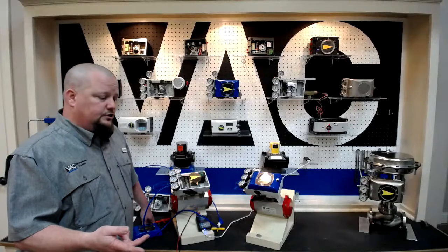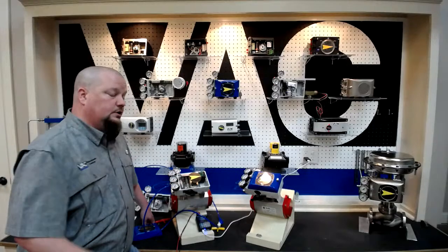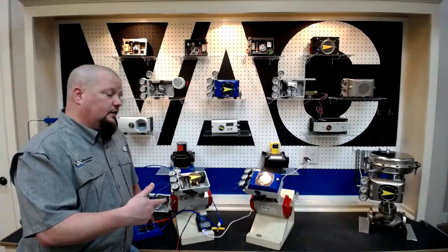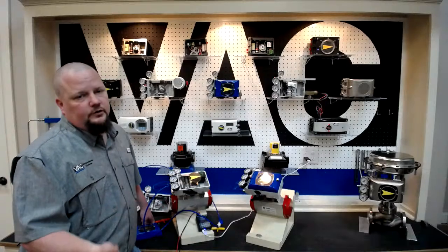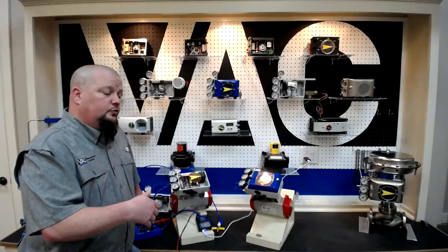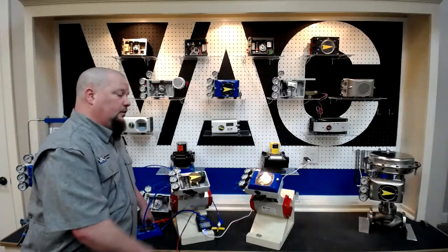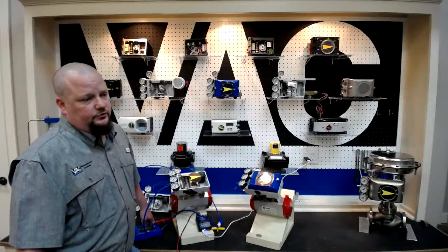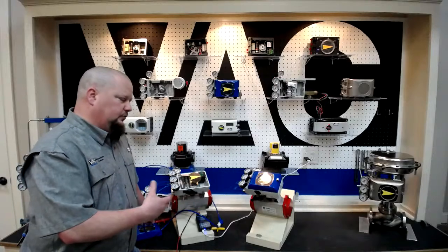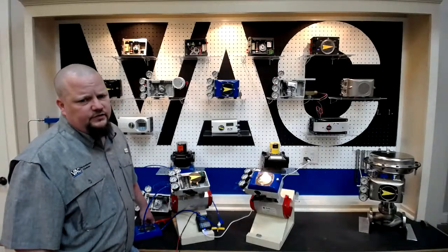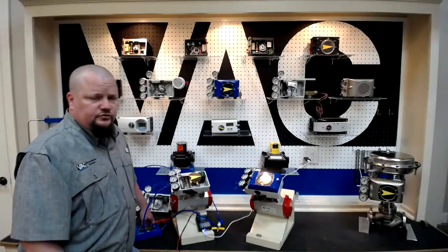we have two types of issues. Once you get into troubleshooting, you've got one where the positioner just doesn't work, and then one where it exhibits some behavior that's undesired, meaning as soon as you give it signal, it goes full open, any signal. Or as soon as you put air on it, it goes full open and it should be closed. Those are the type of things we're now going to look at, and we're going to demonstrate a couple of them and how to fix them. And they're the most common issues we see.